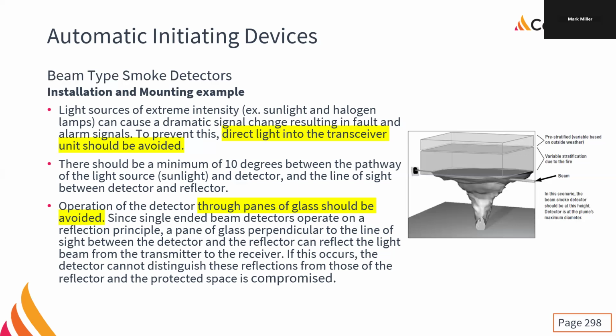The nice thing with beam detectors is because they are not mounted right up at the ceiling, cold smoke becomes less of an issue, right? When we're talking about large areas, stratification of the smoke becomes much more significant. And so by mounting them lower, we get to skip that problem entirely.